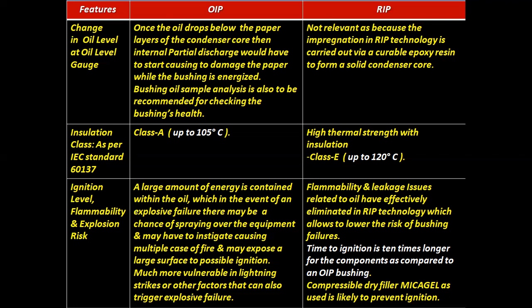Ignition level, flammability, and explosion risk. For OIP bushing, a large amount of energy is contained within the oil, which, in the event of an explosive failure, may spray over the equipment and associated equipment, causing multiple cases of fire and exposing a large surface to possible ignition. It is much more vulnerable to lightning strikes or other factors that can also trigger explosive failure.